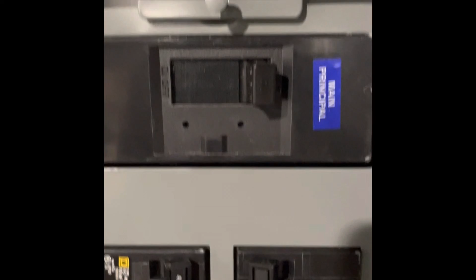The utility, my township, the state, and the National Electric Code are not going to trust that I'm going to be here to turn off this breaker when a utility worker starts work on a power outage, should there be one. The end result is that circuit is open from the 90 amp breaker through my main breaker and back into the utility wires. And that is dangerous. So we need another device.